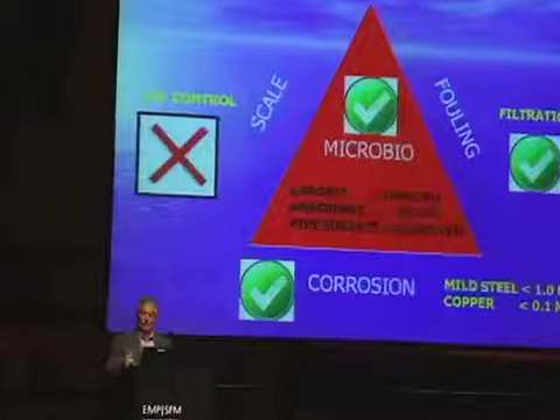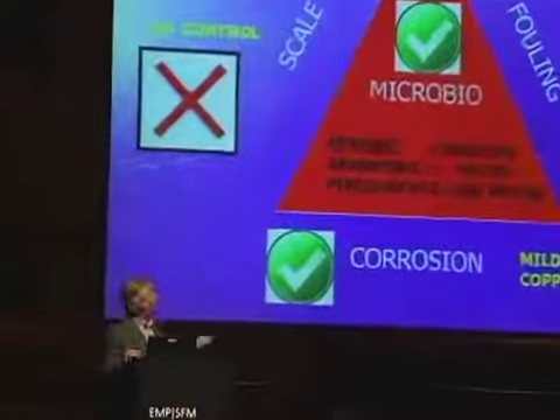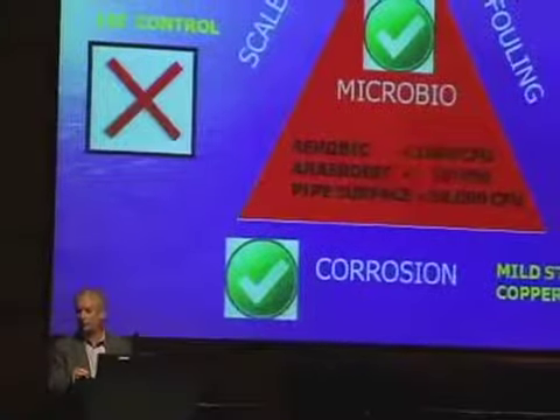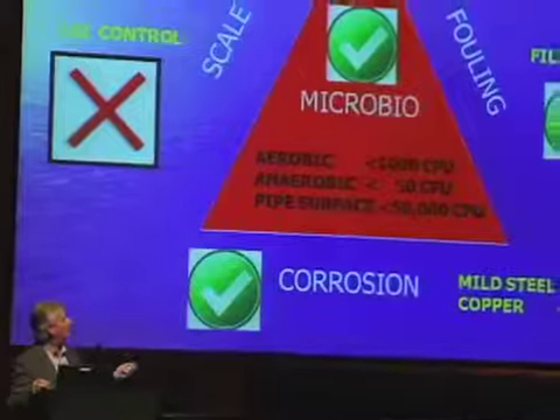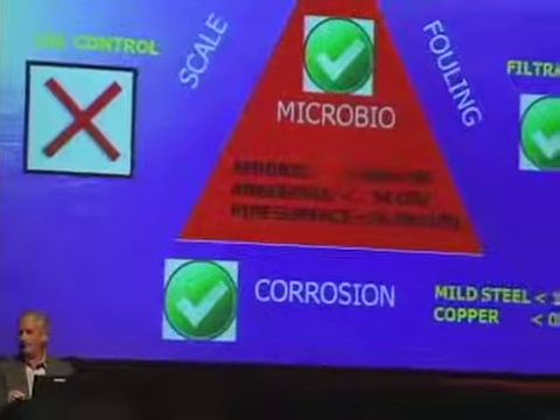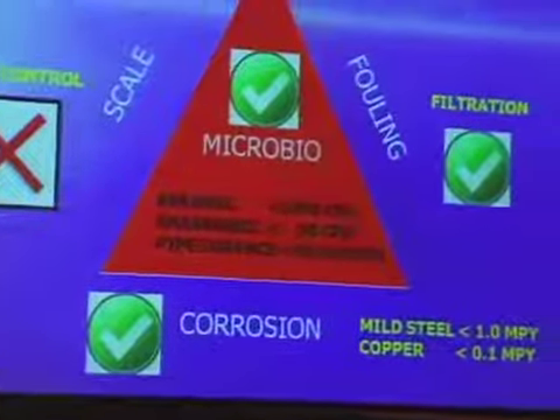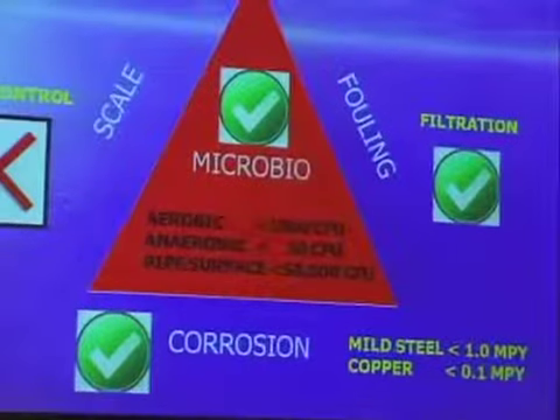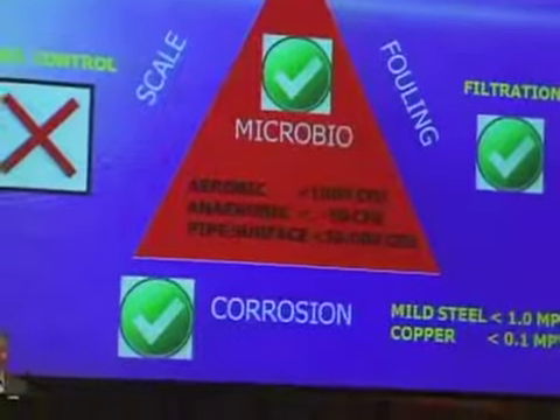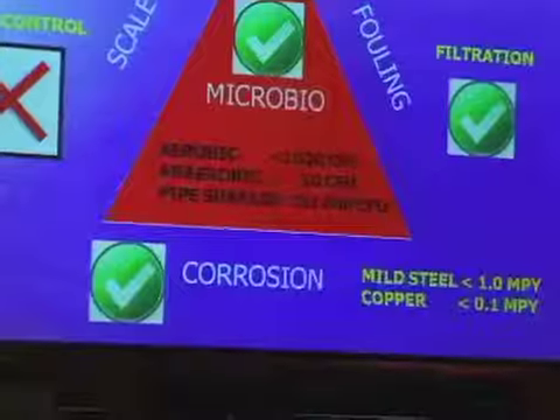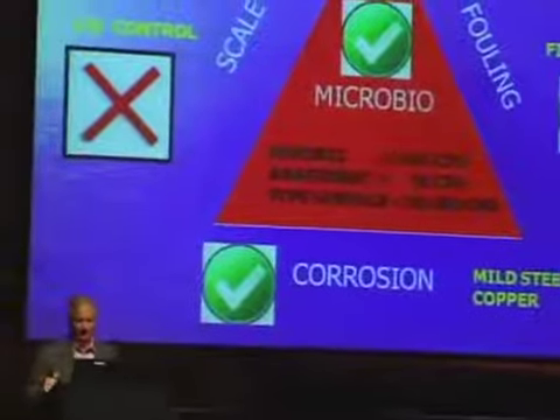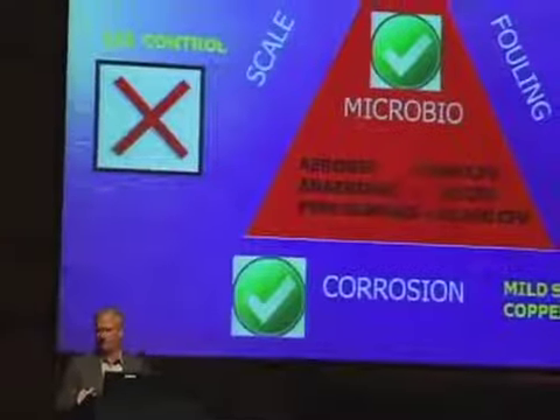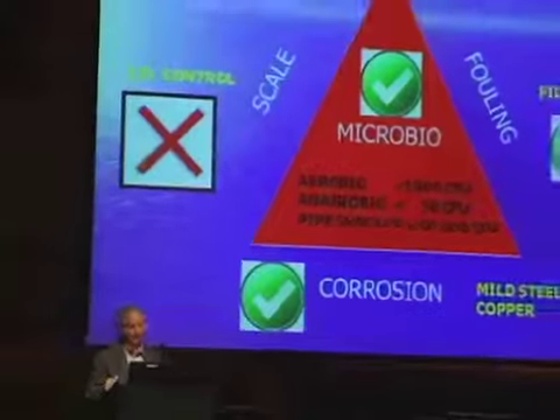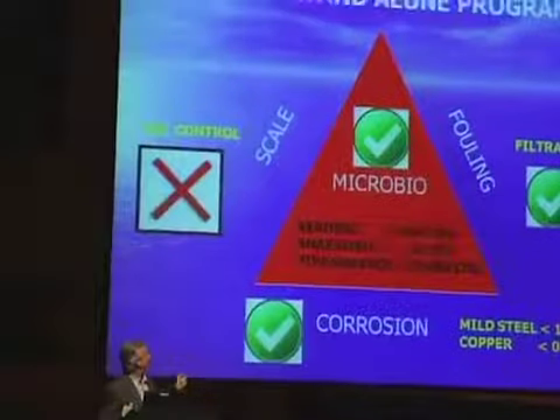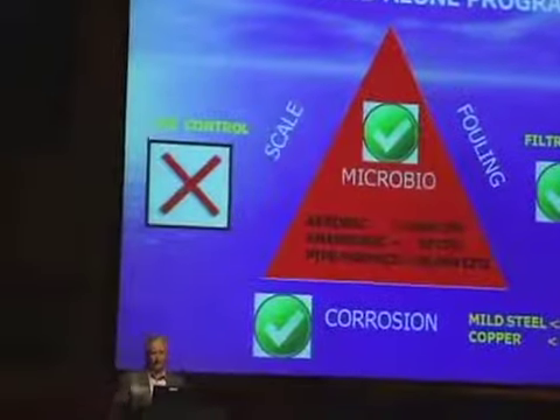Because ozone did a very good job biologically, we saw very good biological control, and because there wasn't much biological activity, we didn't see much fouling. Then, of course, they tried to ramp up the cycles for corrosion control - the only problem is it had nothing to do with scale, and every tower scaled because of it. So it failed there, and it only covered 3 of the 4 quadrants it needed to work on.